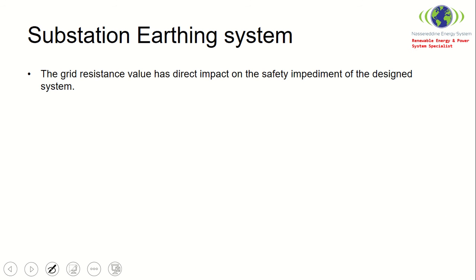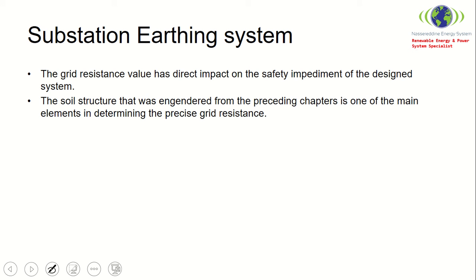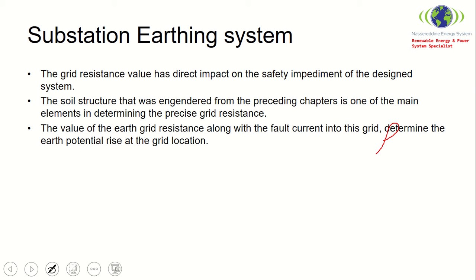The grid resistance value has a direct impact on the safety of the design system, as discussed in previous lectures. The soil structure — determined in the preceding chapters — is one of the main elements in determining the precise grid resistance. So now we go back to soil resistivity. The value of the earth grid resistance, along with the fault current into the grid, determines the Earth Potential Rise. The earth grid of an earthing system consists of several configurations.